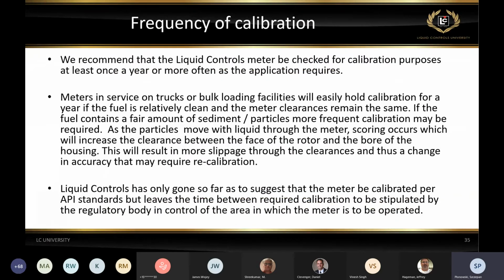A question that comes up very often is, how frequently do we calibrate? Liquid Controls is not necessarily a governing body as far as the frequency of calibration. We generally recommend that meters should be checked annually, or as often as the application requires, which means if the meter is used very often and a large volume of product goes through the meter all the time, it may have to be checked more frequently than once a year.